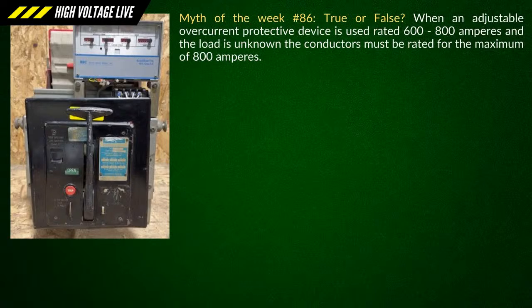So if you go into Table 250.122, it'll basically give you one equipment grounding conductor that's compliant for 600 amps and a different size equipment grounding conductor that's compliant for 800 amps. So you have two different sizes to look at. You have to think, am I going to size to the minimum? What happens with this adjustable breaker if you have to go larger than 600? Regardless, you're permitted to protect the conductors at whatever.